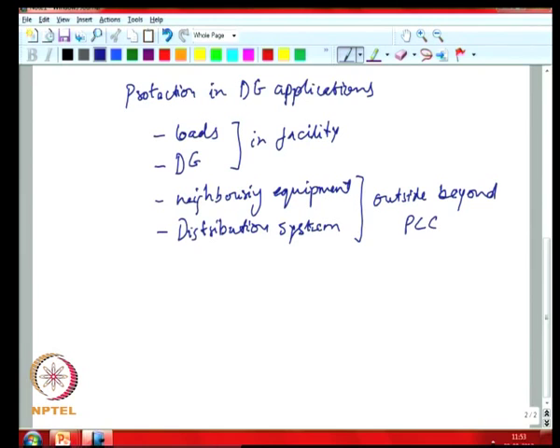Your protection is not just behind your point of common coupling — it is also upstream of the point of common coupling. When you are incorporating a source you need to actually ensure that the protection is adequately accomplished. You need to identify zones of protection with overlapping protection between zones, and potentially backup protection. Once you have protective relays you need to think about their settings and what faults you are trying to protect against.